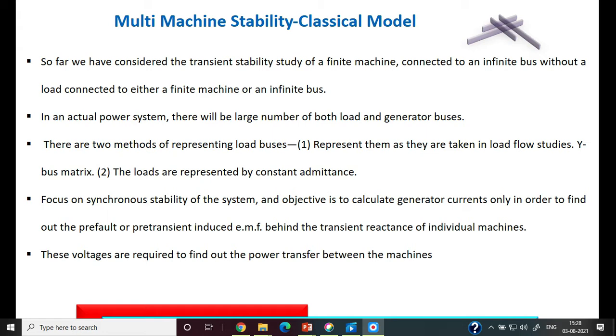The objective is to calculate the generator current in order to find out the pre-transient induced EMF behind the transient reactance of individual machines. In the case of a symmetrical fault, there is a variation of reactance in three different periods: sub-transient, transient, and steady-state. Under transient conditions, we represent the voltage behind the transient reactance for analysis purposes.